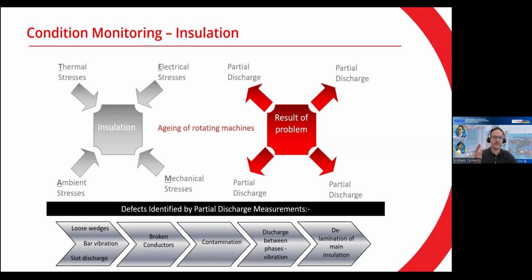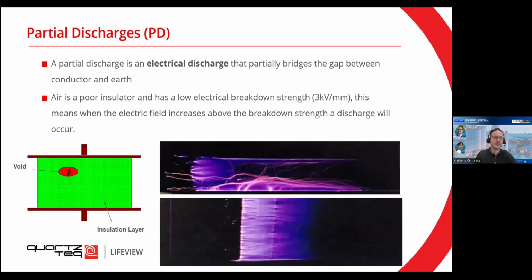You can have vibration, broken conductors, contamination, delamination of the insulation. And all these problems will then emerge as partial discharges. So you're going to have partial discharges inside your machine. This is a bit like a snake chasing its own tail. The more issues you have in your machine, the more partial discharges you're going to have. And the more partial discharges you have, the further the health of the machine is going to decrease. So what are these partial discharges that I was just telling you about?